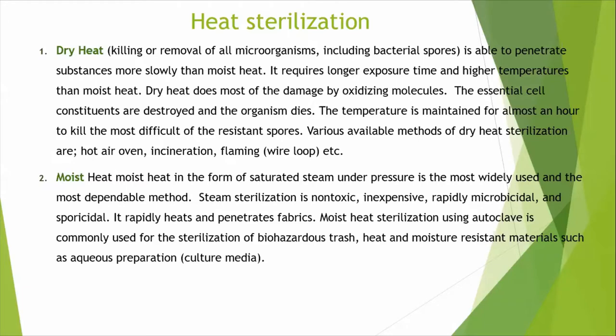Dry heat is the killing or removal of all microorganisms including bacterial spores. It penetrates substances more slowly than moist heat, requires longer exposure times and higher temperatures, and does most of its damage by oxidizing molecules — the essential cell constituents are destroyed and the organism dies. The temperature is maintained for almost an hour to kill the most resistant spores. Methods of dry heat sterilization include flaming with a Bunsen burner using an inoculating wire loop, hot air oven, and incineration.